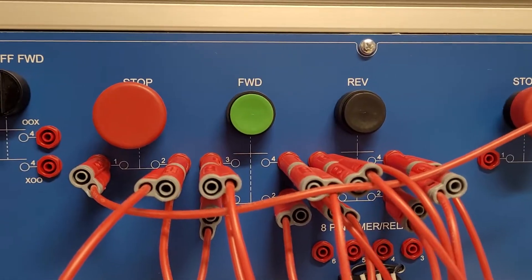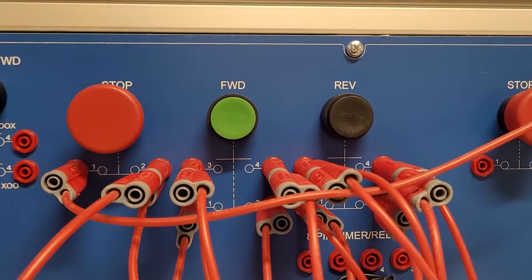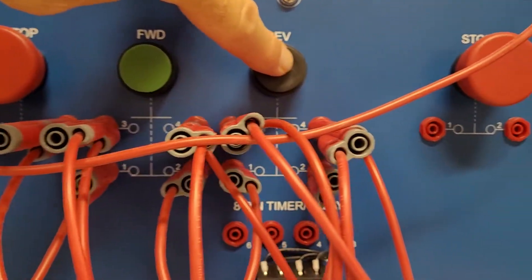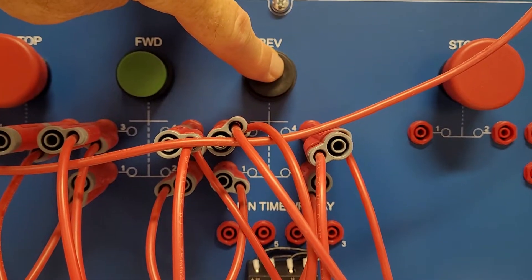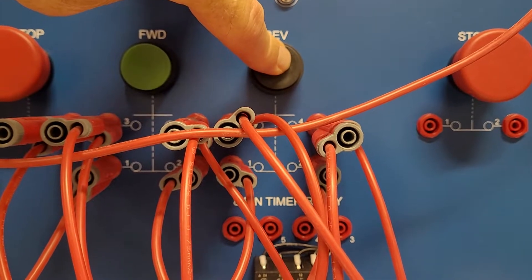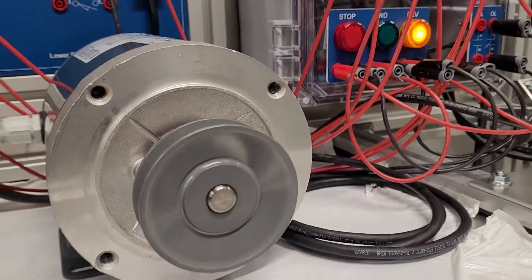So what we're going to do now is we're going to change from forward to reverse. So what happens is when you hit the reverse button, it breaks the contact interlocking the forward circuit, and then it makes the contact that drives the coil on the reversing starter. So now we're in reverse.